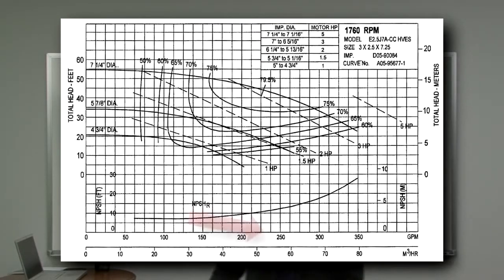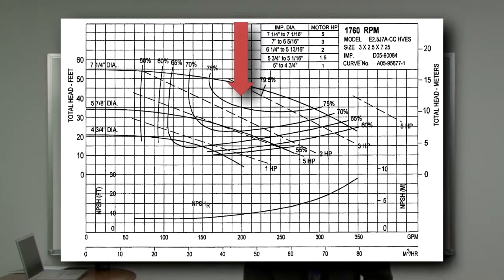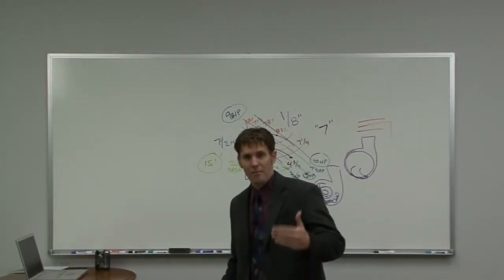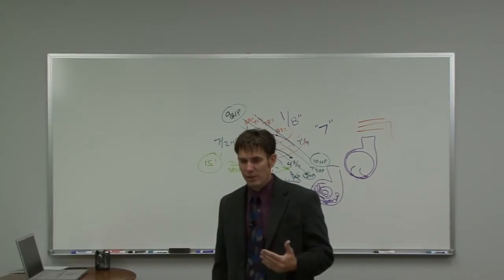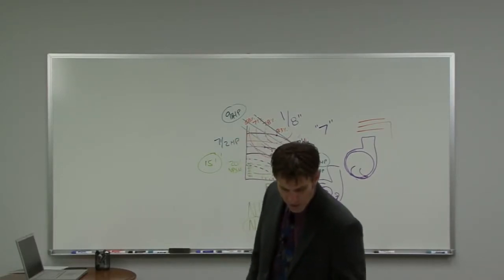Let's say that I'm operating at 200 gallons per minute at 40 feet of head. So across the x-axis is my gallons per minute, my flow rate. Up the y-axis is my total feet of head. You notice that we are sitting in between the 7¼ inch diameter impeller and the 5 7/8 inch diameter impeller. So what impeller trim are we going to use? Well, again, based on that 1/8 inch increment, we could determine what that trim would be.